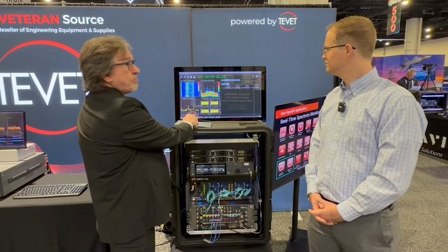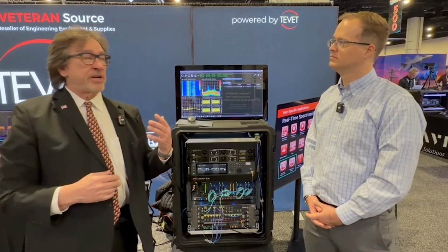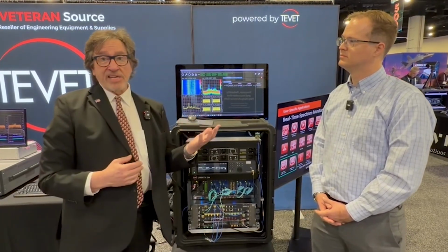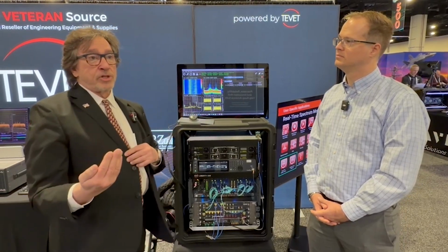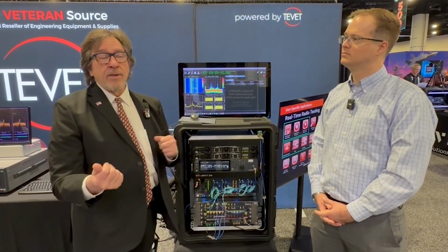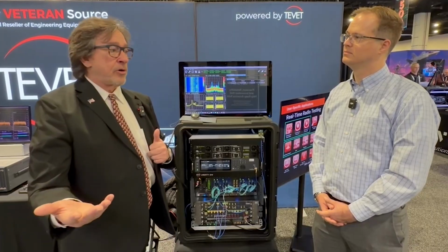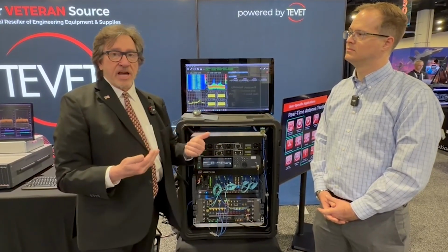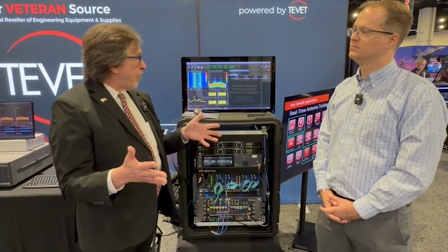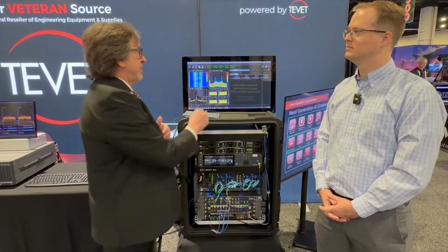That's an important point, because I could set up channel 0 to be frequency mask, channel 1 to be frequency density, channel 2 to be a time domain, or channel 3 to be an external. That allows you to use different types of triggering for the record process.